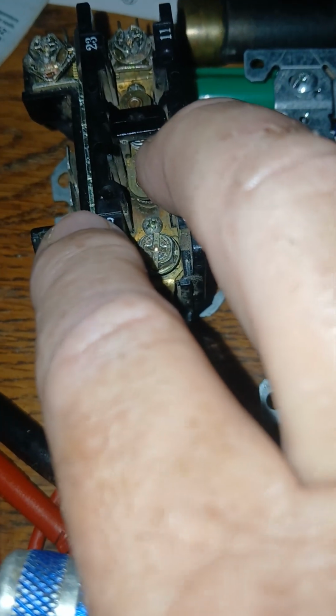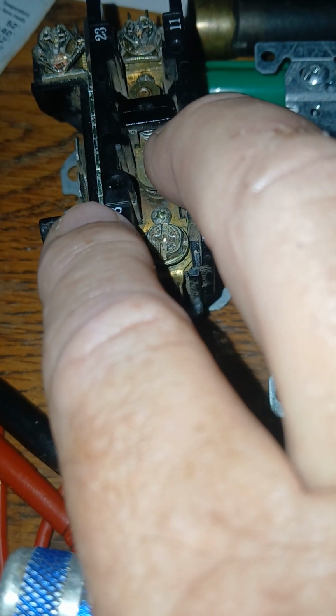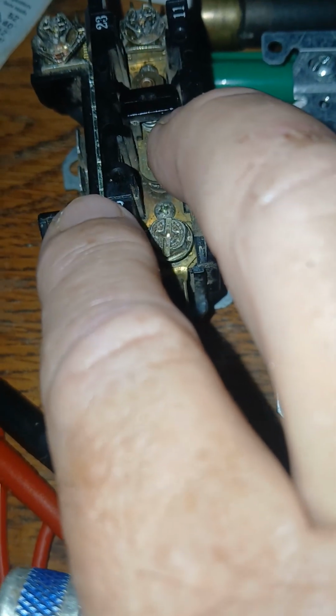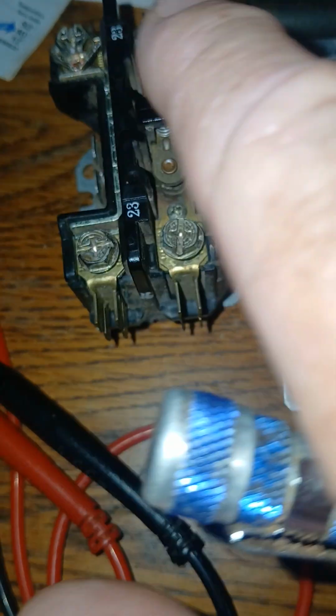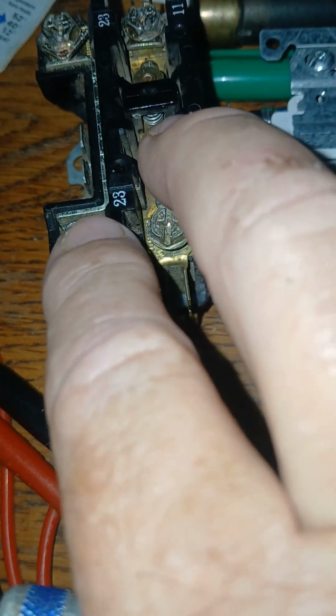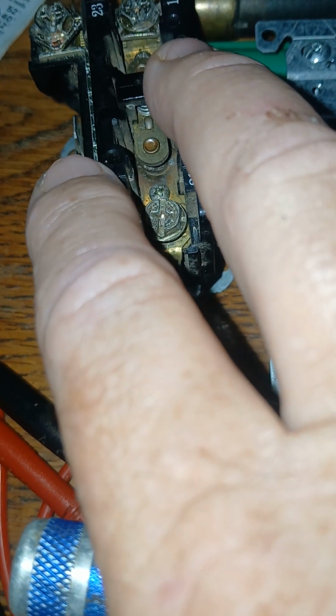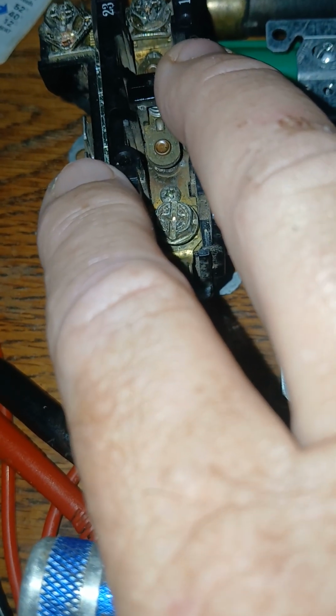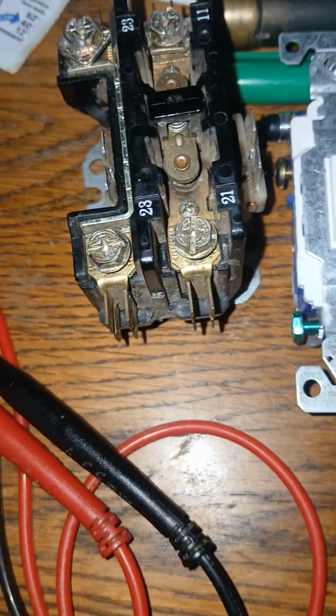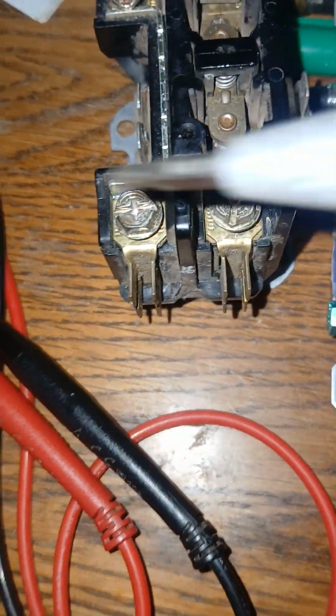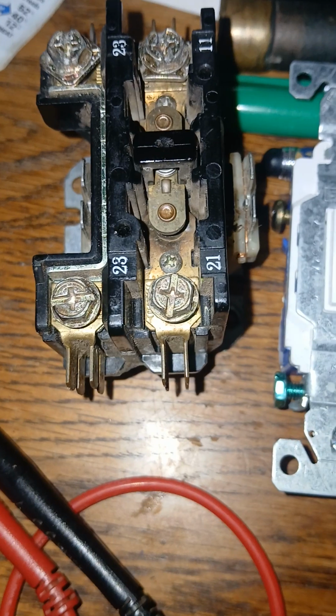Once this coil's de-energized, then the compressor and the fan motor stop. What does that mean? It means that it's not going to continuously or incessantly run, where if it did, it would end up burning the fan motor or the compressor motor up, perhaps. So it conveys electricity, but it may also have the function of protecting the particular unit in your condenser too. So, a quick way to test the coil on a contactor.